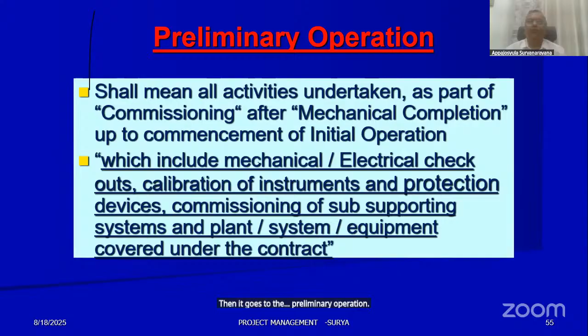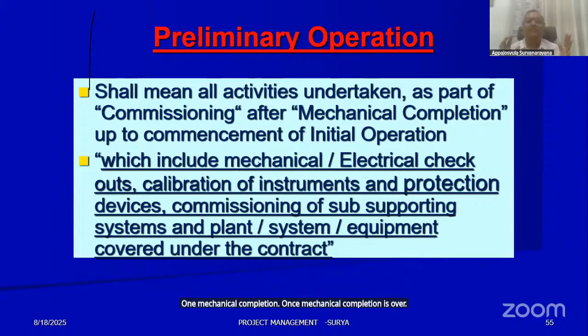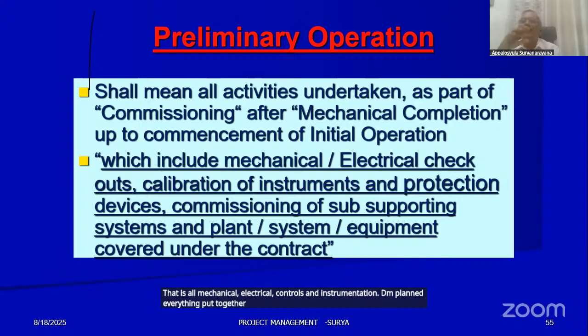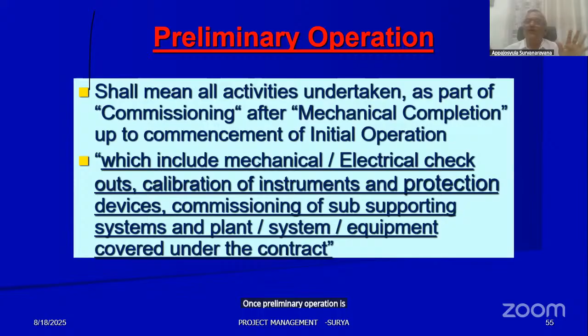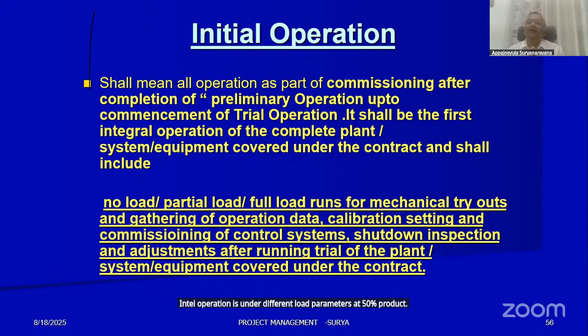Once mechanical completion is over, we conduct the preliminary operation - integrating mechanical, electrical, controls and instrumentation, DM plant, everything together. Once preliminary operation is allowed, it goes to initial operation, meaning under different load parameters at 50% or 100% load, checking whether the plant maintains the norms. Then comes trial operation, a contractual term meaning the plant has to run for a specified number of days at a particular load.